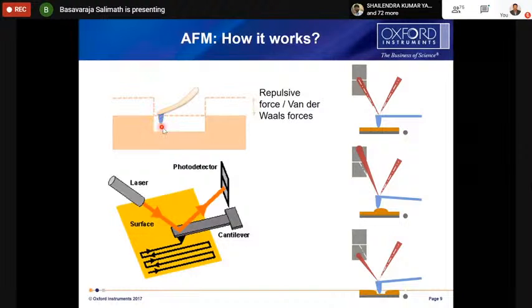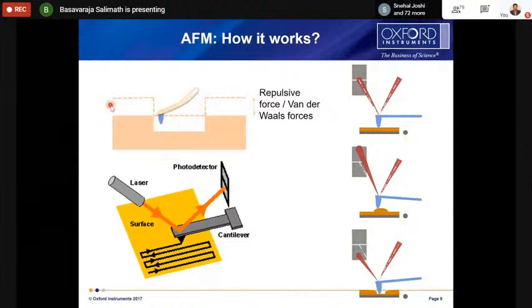So when this tip comes to this place, what will happen? Here, because of this wall, it will experience more repulsive forces compared to this place. So that's why the tip will automatically go up. Like this, because of the forces present on the sample and also because of the applied force, our tip or cantilever is following your surface roughness. Now we know that the tip is following our surface roughness, but we don't know how much the tip is actually moving up and down. That we don't know.